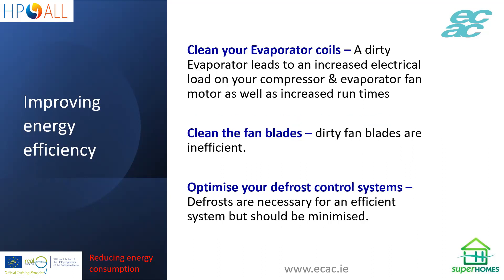Clean the evaporator as well. The evaporator may be a little bit more difficult to clean and people sometimes ignore it, but it does get dirty, particularly in supermarket environments. If the evaporator gets dirty, it reduces the airflow over the evaporator, causing the evaporating temperature to decrease, which in turn causes the compressor to have to work harder and increases the duty on the fan motors. What people rarely do is clean the fan blades. Dirty fan blades are inefficient — the blade shape is designed to move air as efficiently as possible, and as dirt builds up on the fan blades, the efficiency of the fan motors drops.